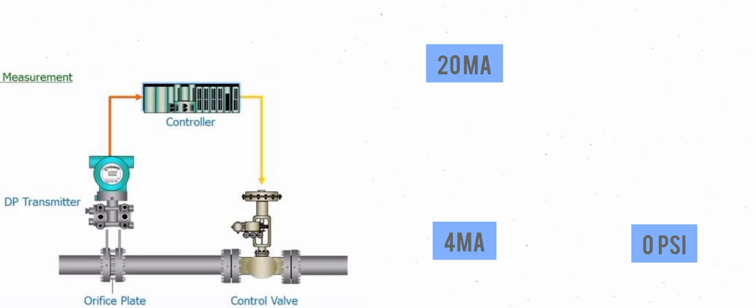Depending on the range of measured pressure, a 4 milliamp signal would equal a measured differential pressure of 0 psi and a 20 milliamp signal would equal the maximum measurable value. In this case, we'll say that the maximum differential pressure is 100 psi.